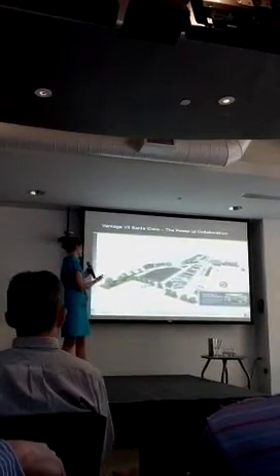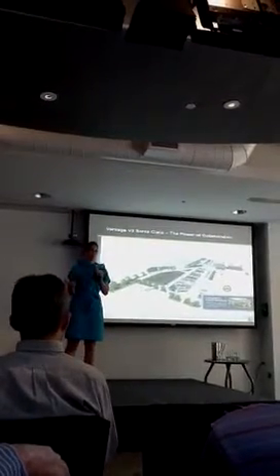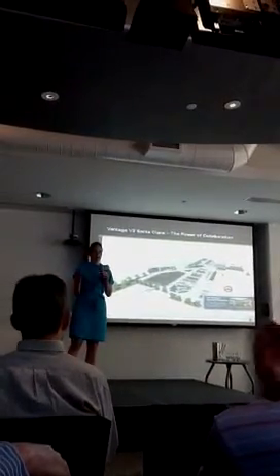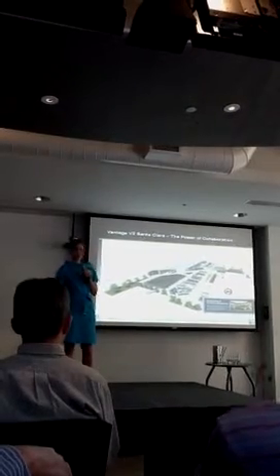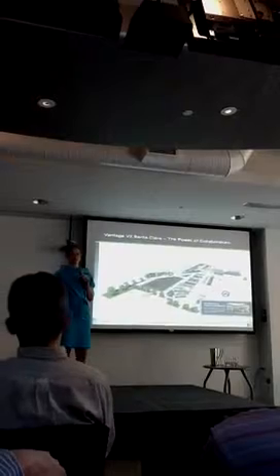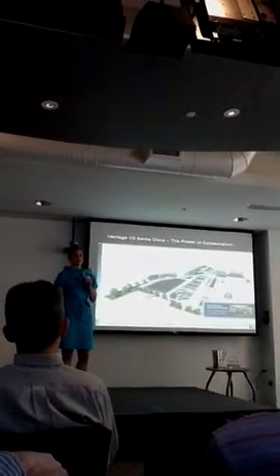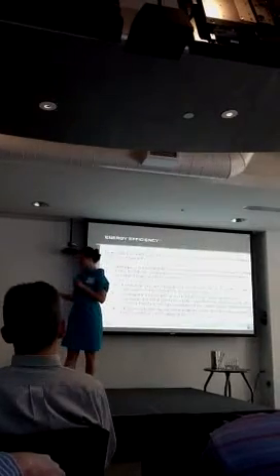It goes through the filters into the supply air plenum and across coils. In addition, we have bypass so that we don't have to go through the coils all the time. But we kept the velocities really low so that it was successful regardless of whether you're running in mechanical cooling condition or if you're running in outside air economizer condition.